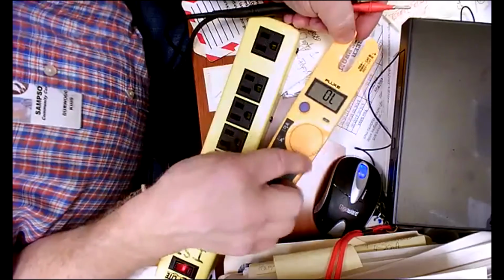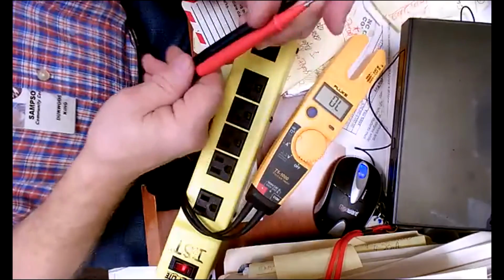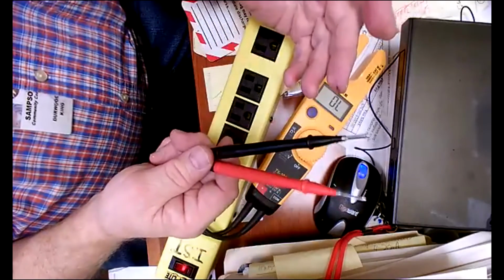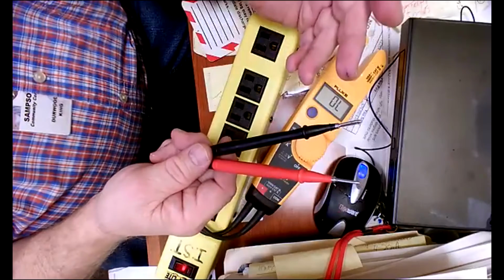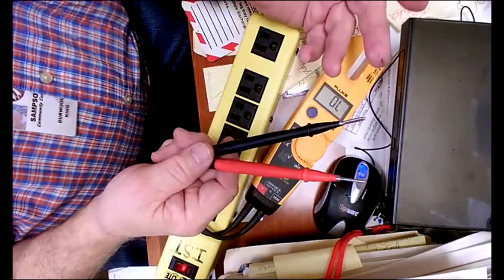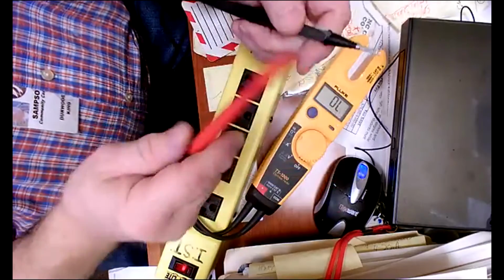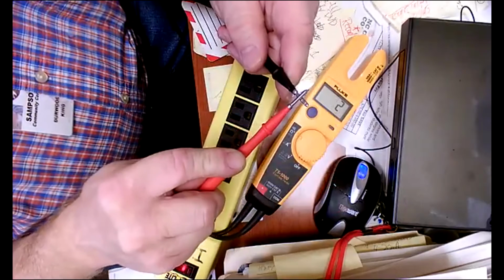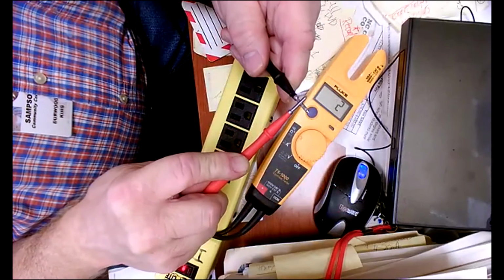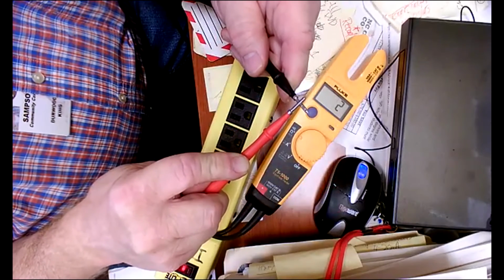I'll check mine. Basically, here's what you want to do: if you're checking the resistance of a heater element or something that's got ohms to it, and you want to know is the ohm reading of the heater element okay or not, the first thing you do is you put these together and whatever number that is, you would subtract that from the reading you get on the heater element.